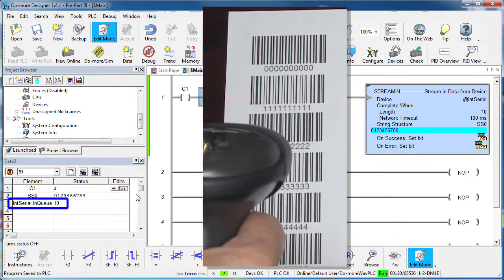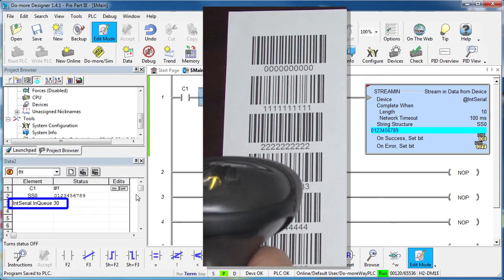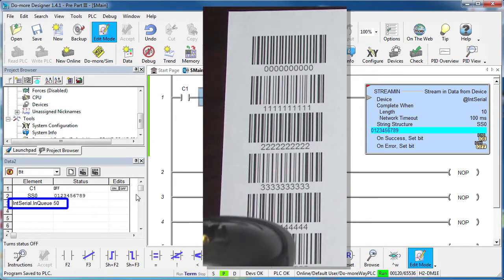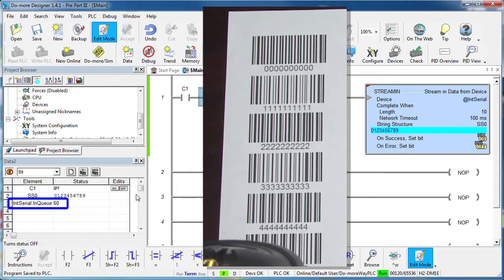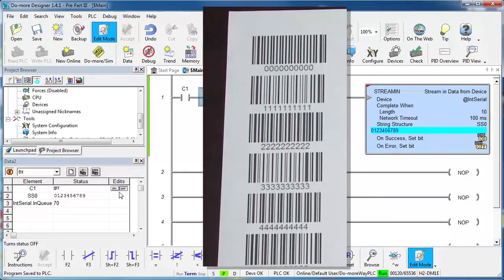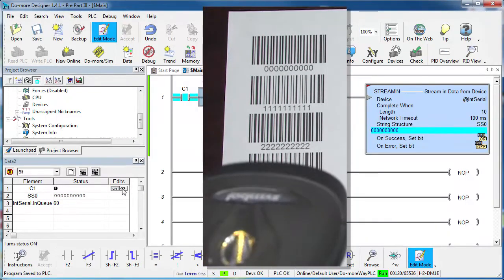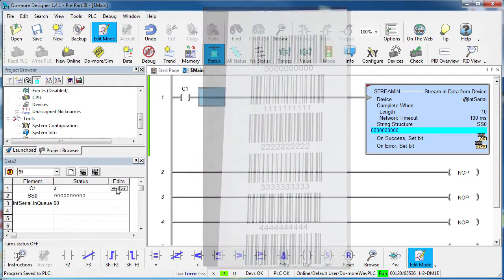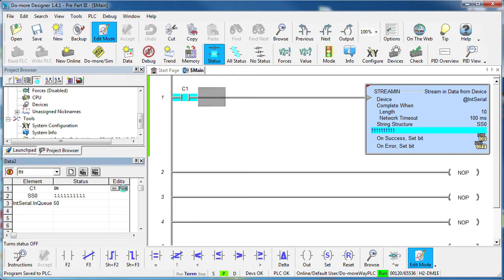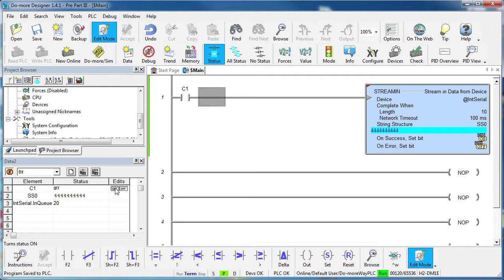If I scan several 10 character barcodes, we see the in-queue increment accordingly and each time we toggle the C1 bit we pull another 10 characters out of the buffer. The point here is the internal serial port device is doing all the work for us. It collects the serial data, puts it in a buffer, increments the character count in the buffer, handles any necessary handshaking.